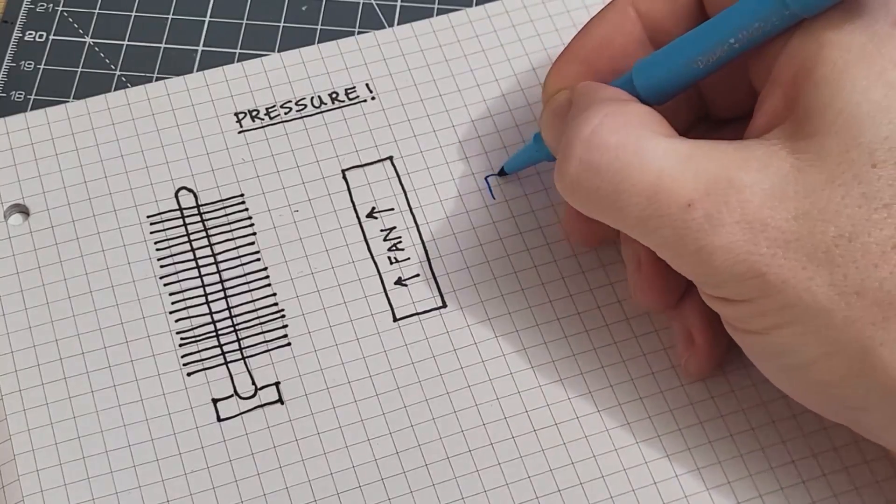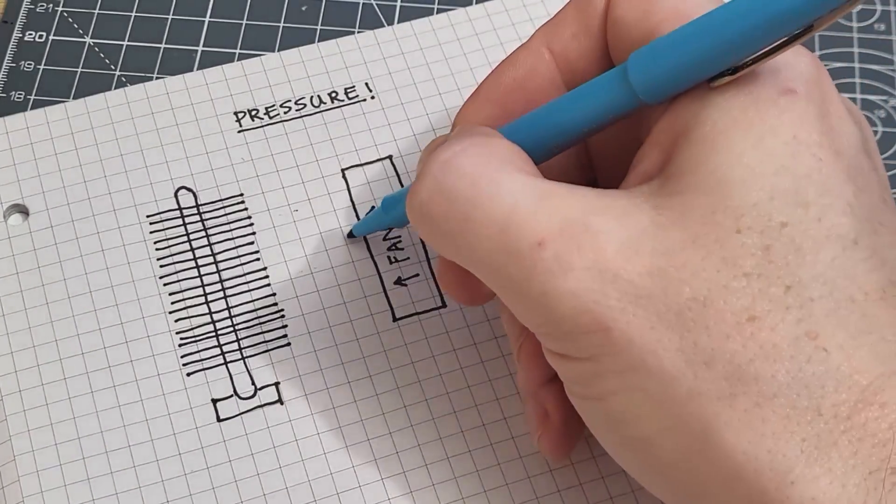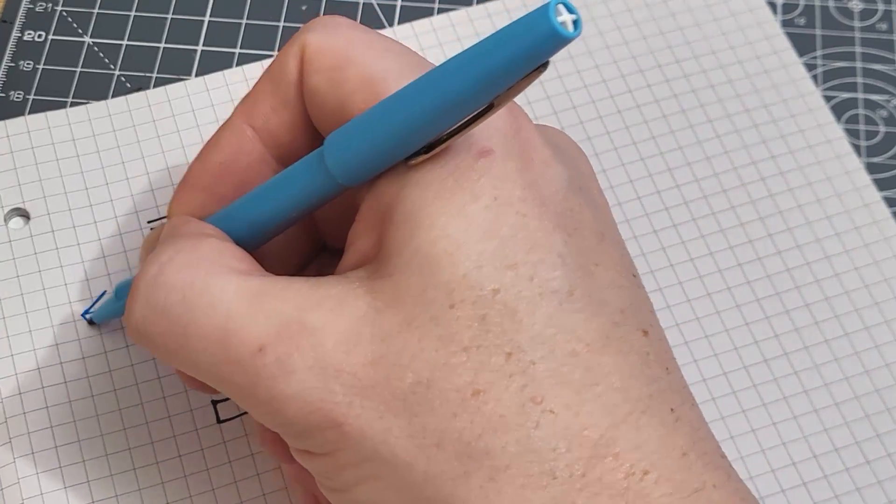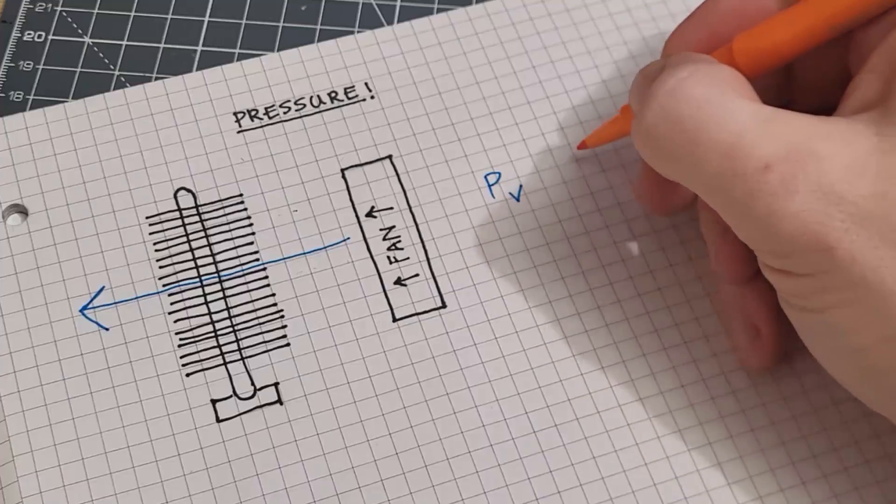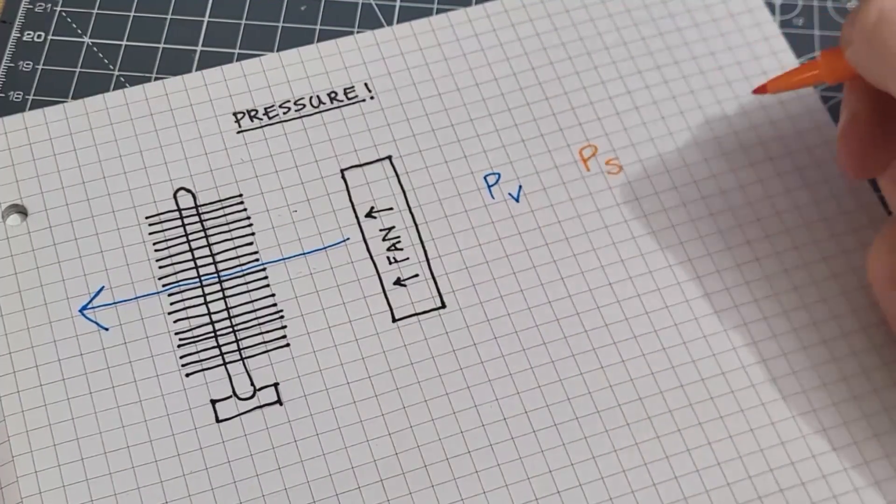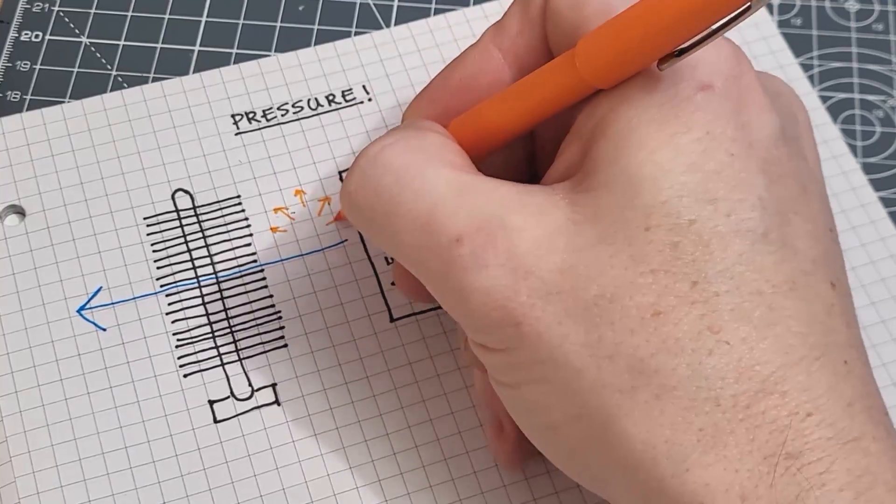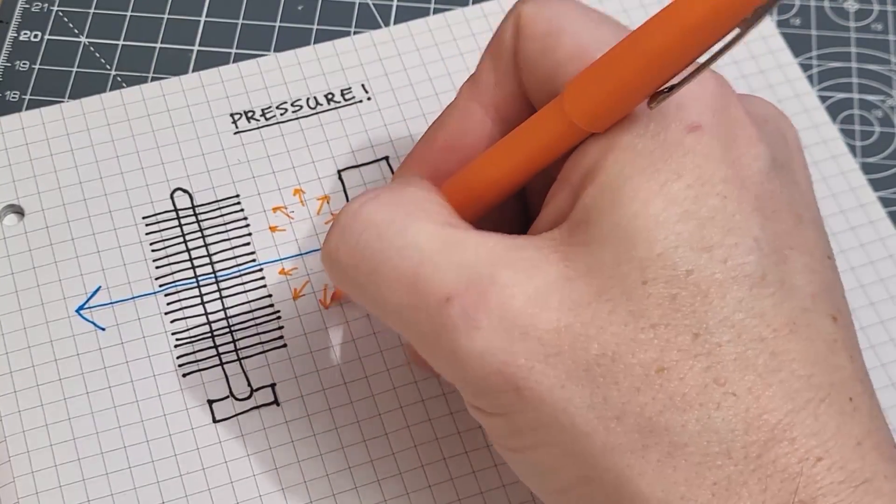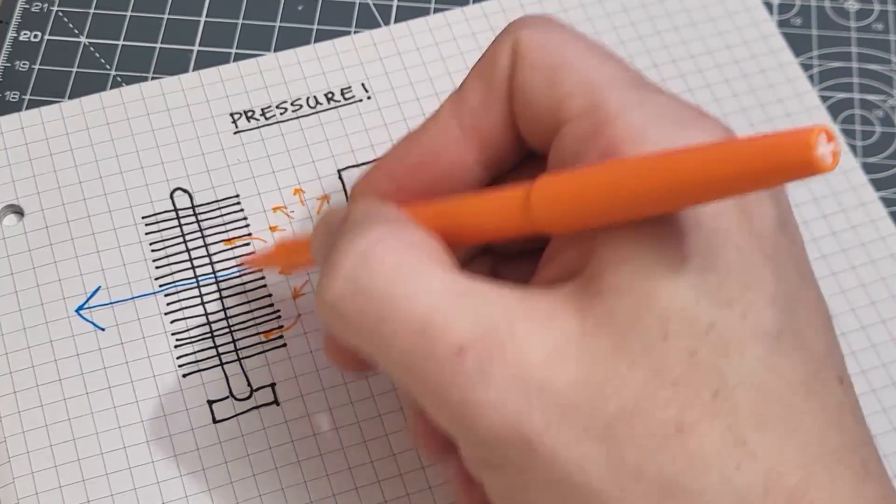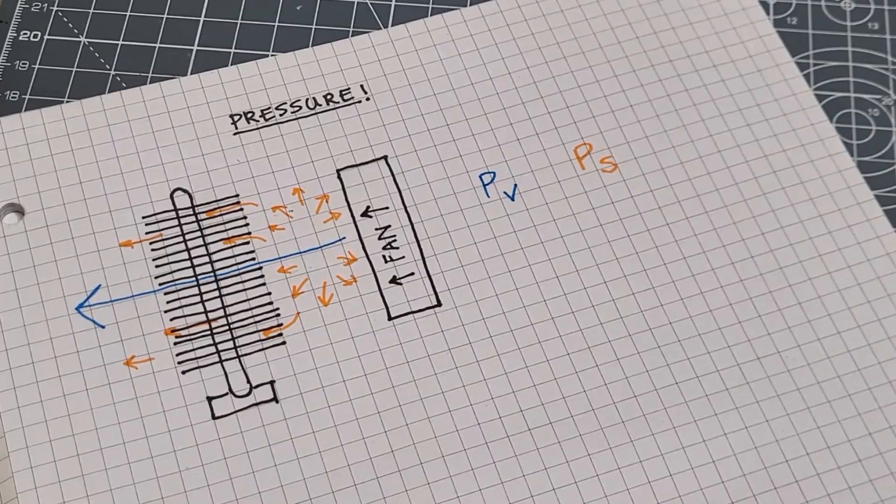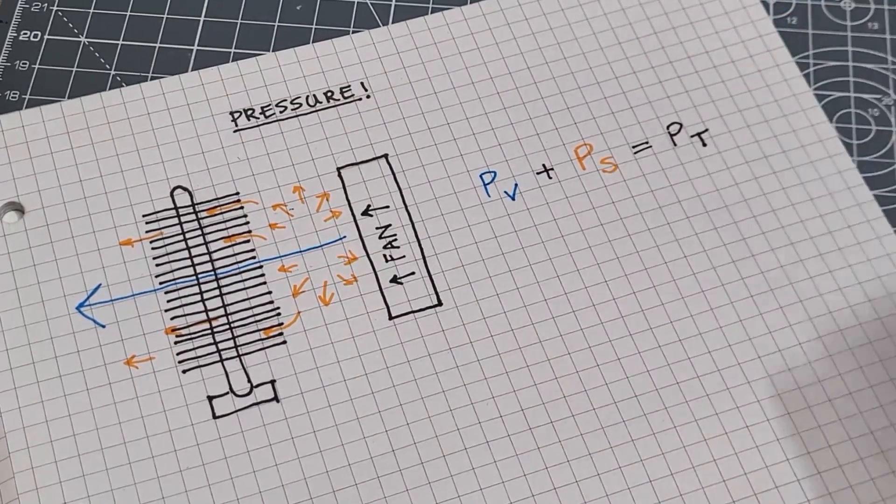It helps to think of airflow in terms of pressure and there are two pressures that we need to consider. First is the velocity pressure which is relative to the speed at which air moves through a given system, and second is the static pressure which as we have already established is caused by resistance to flow. In this system it's the heatsink. Static pressure is relative to the density of the fluid, especially a compressible fluid like air, and therefore it pushes out equally in all directions. Because of this it is added to the velocity pressure giving us the value we call total pressure.